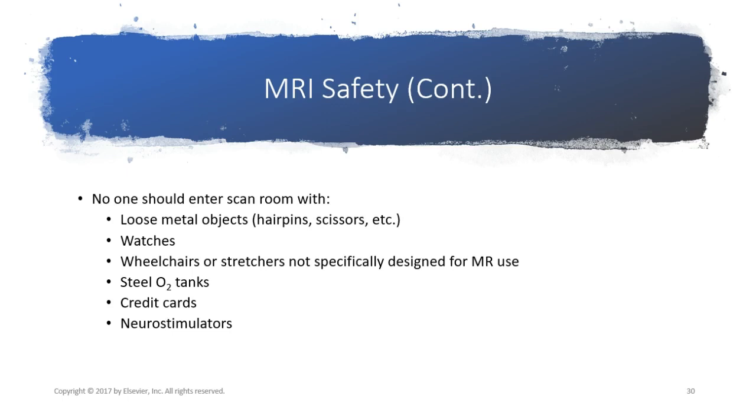Wheelchairs or stretchers not specifically designed for MRI cannot go in the room, so you have to grab the ones that are. Steel O2 tanks, and even if they're MRI safe oxygen tanks, you need to make sure your regulator's safe also. So don't take your credit cards in.